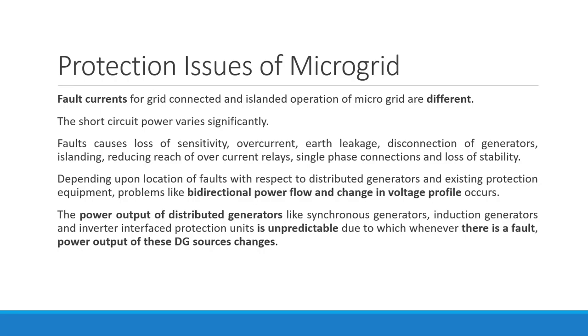Fault causes loss of sensitivity, overcurrent, earth leakage, disconnection of generators. If a fault is there, possibly some generators will be disconnected. Islanding: the microgrid will be disconnected from the grid and will operate independently. Reducing reach of overcurrent relay. Single phase connections, possibly three-phase is there, so single phase connection would be there. And loss of stability. So these are the possible problems which could be due to a fault or faults.